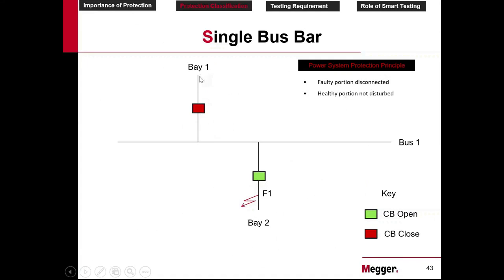So here we have three parts, bay 1, bus 1 and bay 2, three areas. The fault occurred in this area. So this area is healthy, this area is healthy, and this area is faulty. Hence, the faulty portion alone should be disconnected. The healthy portion should not be disturbed. Both are satisfied. Hence, the second breaker is the right one. So this choice is actually based on the protection principle.